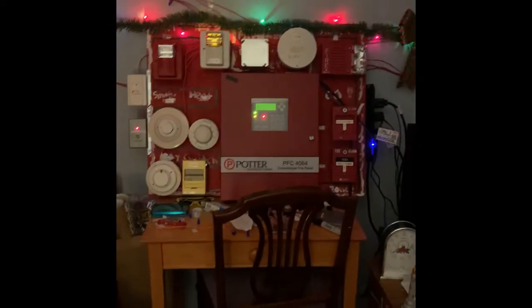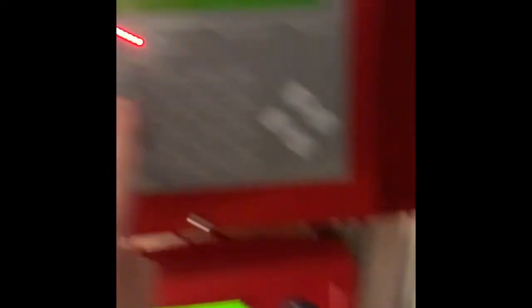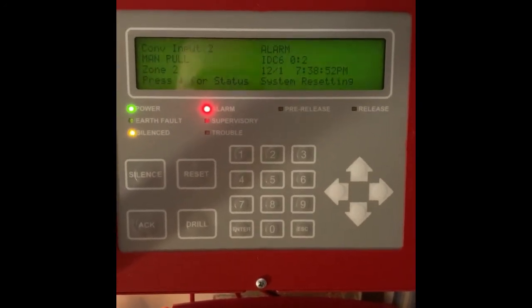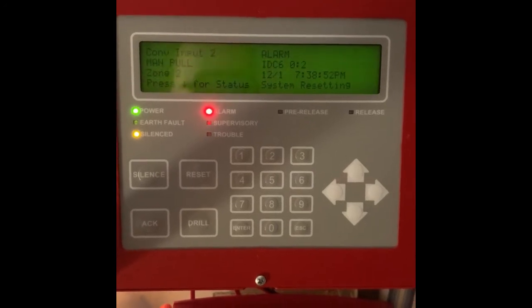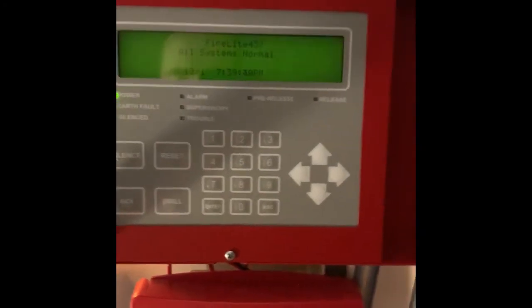We're going to reset from the annunciator this time, and we are also going to reset from it as well. All right, the system's now reset. Now I'm going to go ahead and put the system into walk test, and I'll get back with you shortly. All right, I now have the system in walk test.